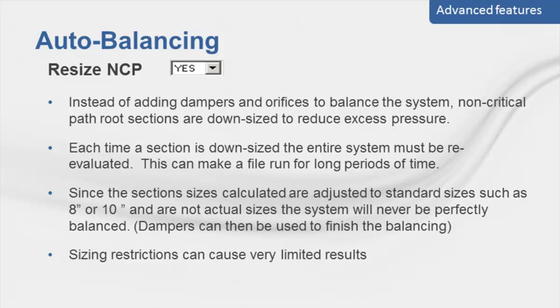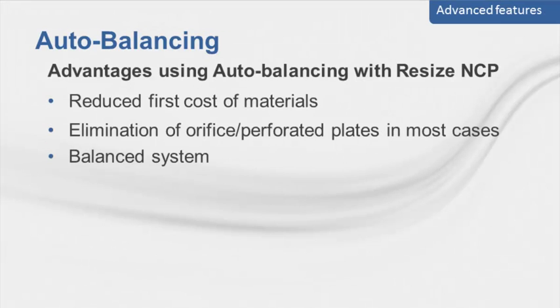If auto balance has already been selected, resize non-critical paths will become available as an option. The program will downsize the non-critical paths of the duct system if possible to decrease the excess static at the terminal devices without affecting the critical path. Downsizing duct sections impacts the entire system, so you should expect calculation times to increase accordingly. Running this feature can reduce installation costs by reducing duct materials without affecting operating costs. Downsized sections on non-critical paths remain within the original design constraints such as maximum section velocity. If some excess static still remains, dampers can further be added by selecting yes in the add dampers and orifices drop-down box.